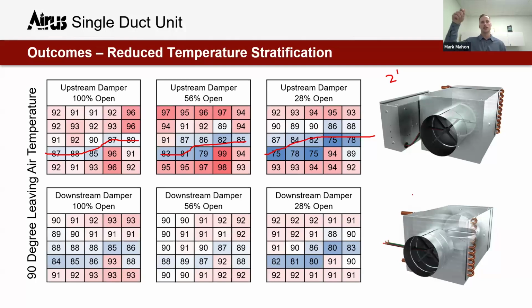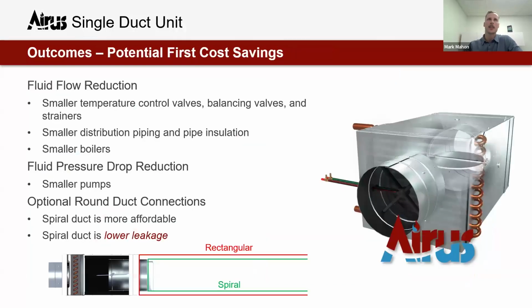And if we think about putting a discharge air temperature probe at a single point, it's possible we could be measuring 82 degrees rather than a mean temperature of 90. It's possible we could essentially be measuring a temperature greatly different than the average temperature being discharged out of the product. Another thing that the downstream damper actually solves in this case becomes a bit of a mixing element after the coil to help reduce that reality.